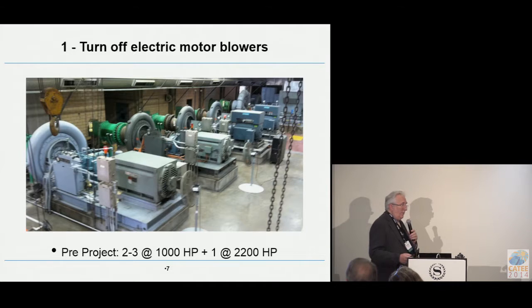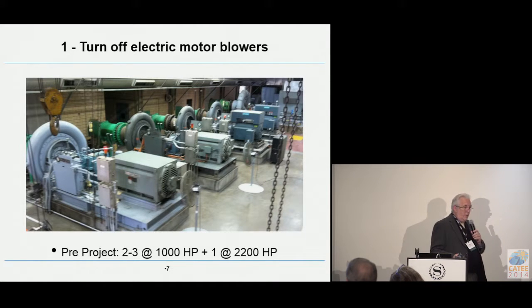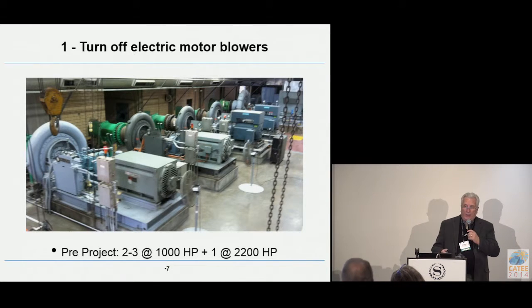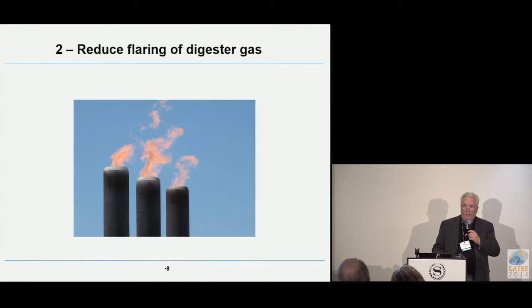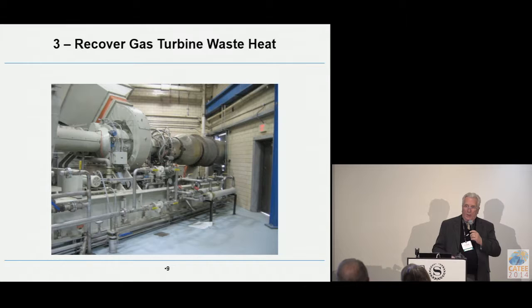That was pretty tricky, but the engineering companies helping us out came up with an idea. They said, yeah, we can take those out of service, and what we'll do is take the gas turbine waste heat and turn it into steam. Then the steam is used to power turbines for our aeration basins. So the single largest consumer of power on the plant site all of a sudden becomes a steam-driven system.